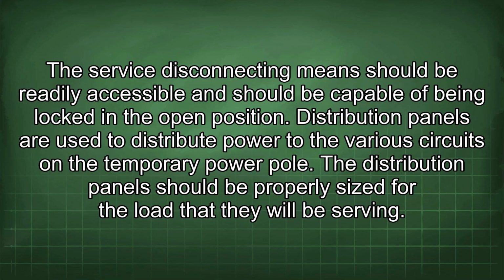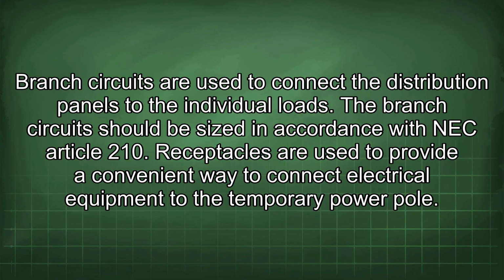Distribution panels are used to distribute power to the various circuits on the temporary power pole. The distribution panels should be properly sized for the load that they will be serving. Branch circuits are used to connect the distribution panels to the individual loads. The branch circuit should be sized in accordance with NEC Article 210.